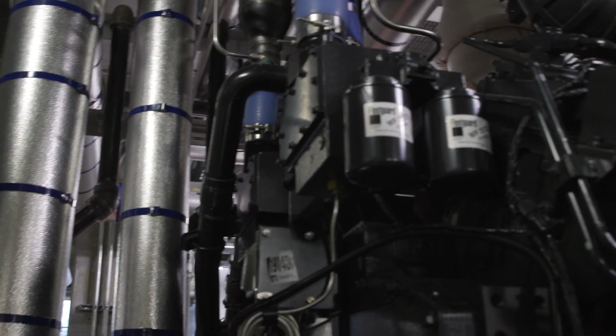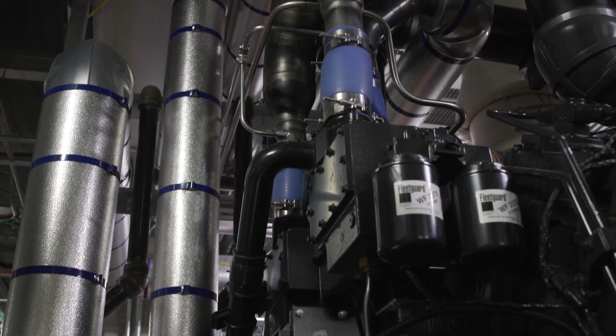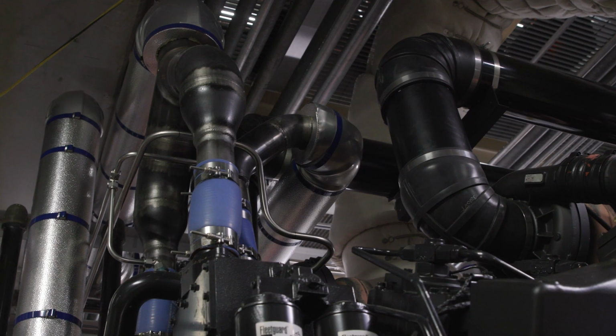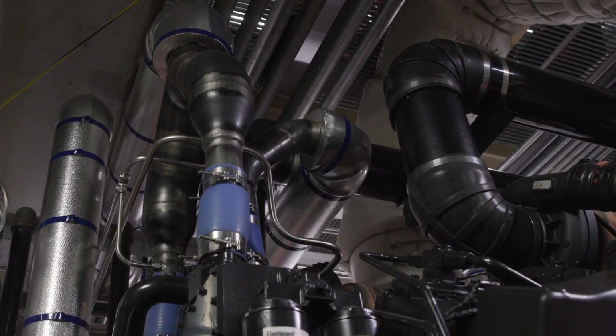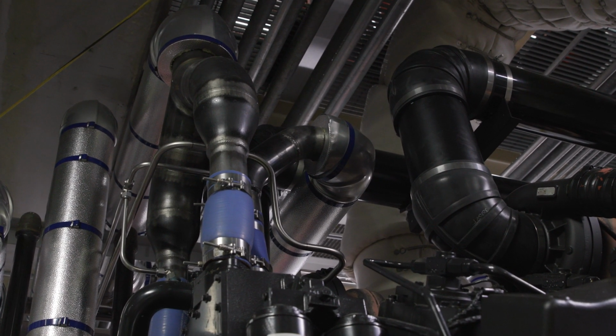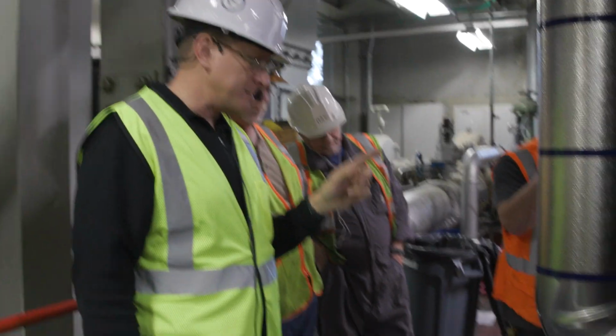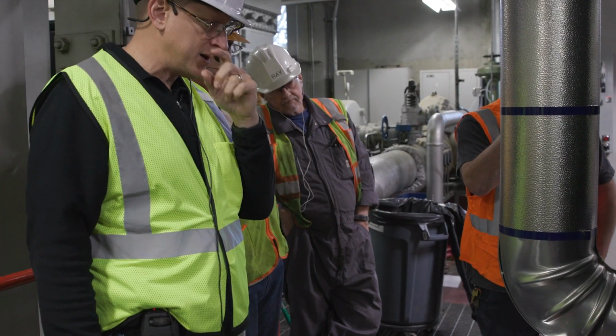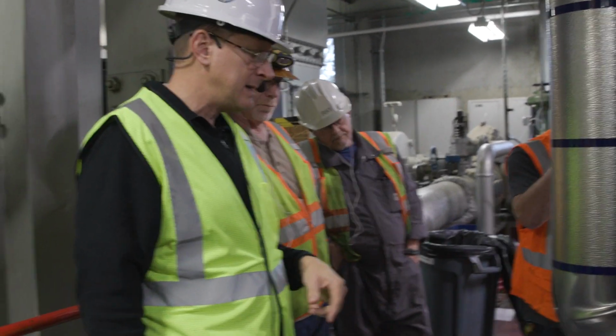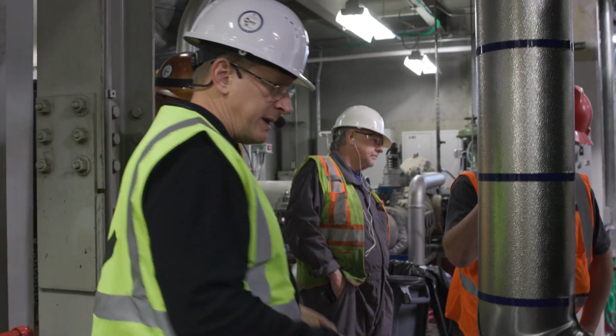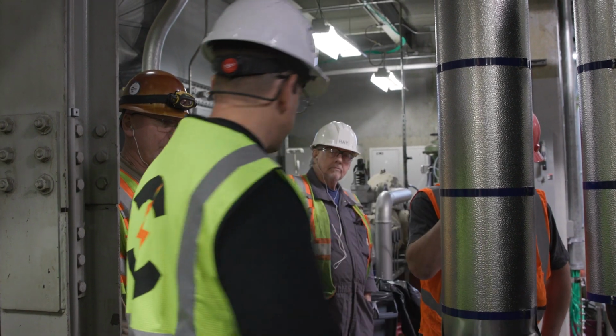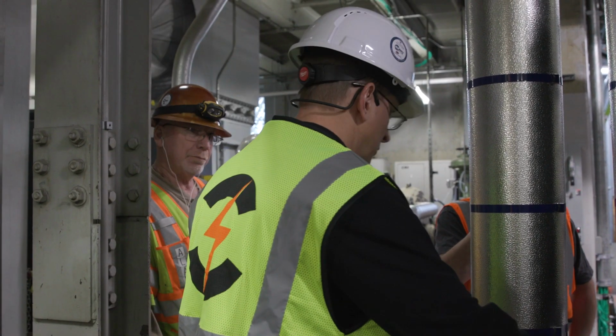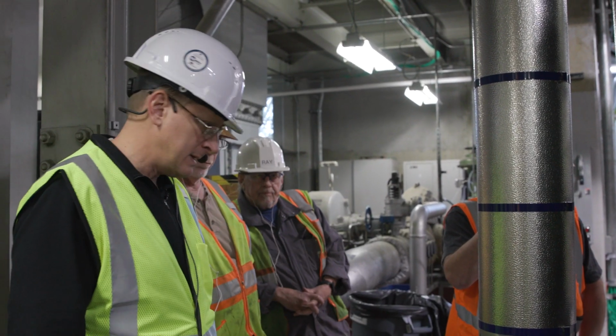Also here on the front of the engine, you've got our preheat. This preheat is sourced from the utility side of the switchgear, from the ATS and the switchgear, the little 45 kVA transformer. Comes through the UCP and into this box here so that we can preheat the engine. Right now it's cold again because everything is shut down, but normally this would keep the engine warm so your block is nice and warm.